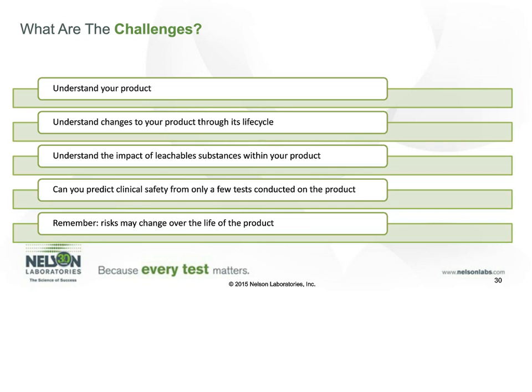And so even though the rule of thumb is that most of the leachables will come off a device right away after it's been processed, the longer something sits around, the more volatiles might come off the device. To limit or reduce the amount of extractables and leachables, still, degradation may happen over time with certain materials, and we have to keep that in mind when we're looking at safety evaluations.